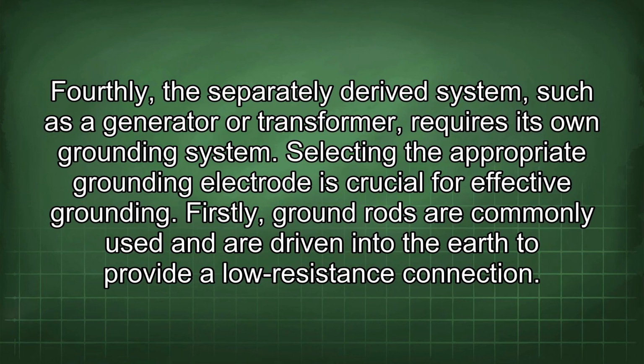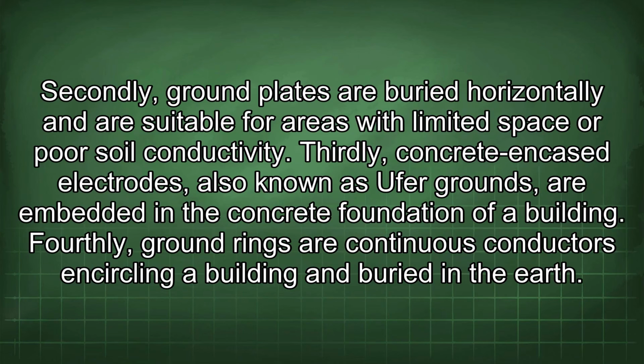Selecting the appropriate grounding electrode is crucial for effective grounding. Firstly, ground rods are commonly used and are driven into the earth to provide a low resistance connection. Secondly, ground plates are buried horizontally and are suitable for areas with limited space or poor soil conductivity. Thirdly, concrete encased electrodes, also known as UFER grounds, are embedded in the concrete foundation of a building. Fourthly, ground rings are continuous conductors encircling a building and buried in the earth.